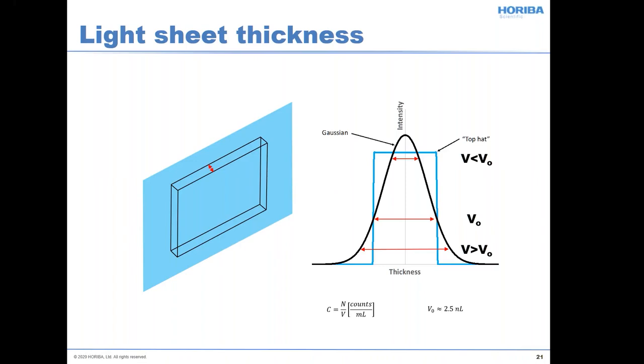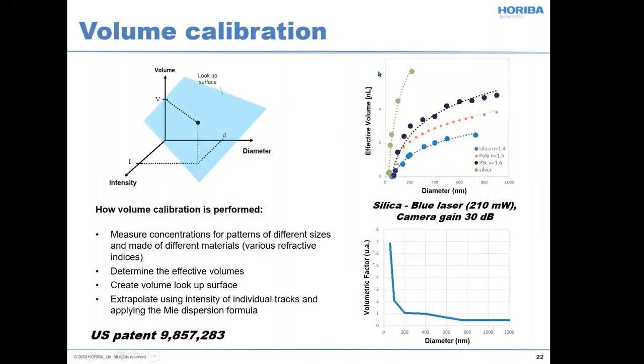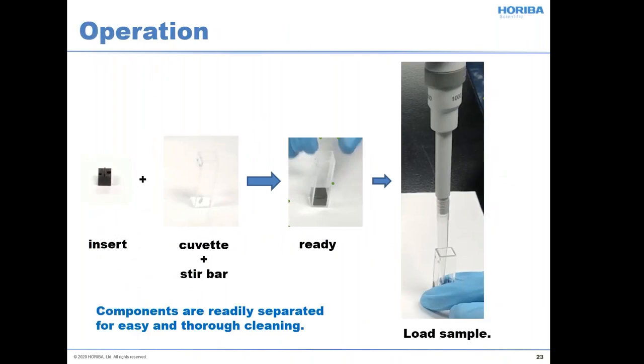There are two key pieces here. The first is the particle-by-particle analysis with the ability to do it over a wide range of particle sizes. The second is getting the correct concentration. Because the instrument works with broad size distributions, this sort of correction is desirable and probably necessary. What we do is create plots of effective volume as a function of particle diameter — those ship with the software — and we have some recommended conditions for various materials. Someone asked me about instrument operation, so I want to add a few slides to cover that.